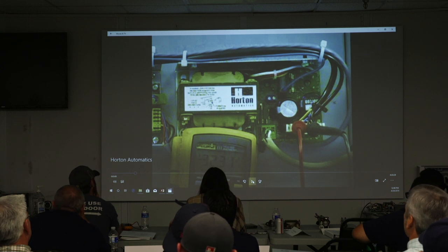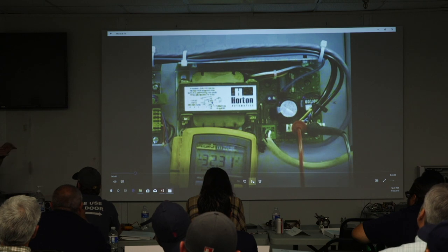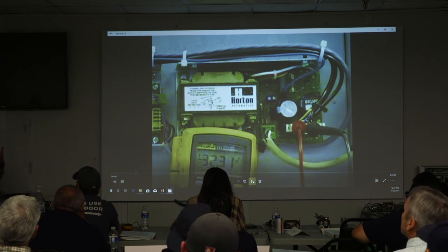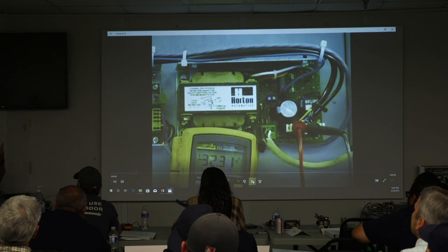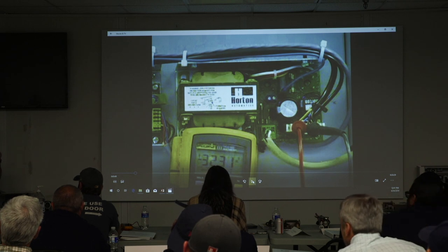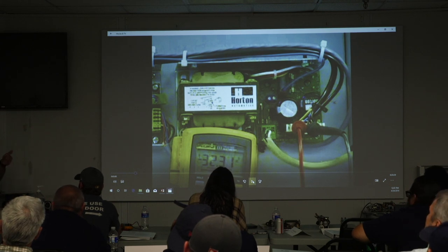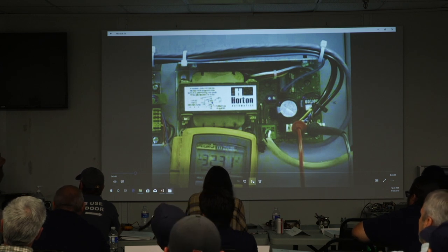Now, what he was talking about there is when you look at those fuses, whenever you're checking it like this, you've got a load against the fuse. And so the fuse is either going to be open or closed. We've seen a lot of times when guys break the fuse out and then check it with an ohm meter, it looks good. They plug it back in, they have no voltage. Well, that meter so lightly loads the fuse that it's back okay again. And he has kind of self-healed himself. Yep. And then they plug it back in and all of a sudden, I still don't have any voltage. What's going on here? Probably got a bad fuse.